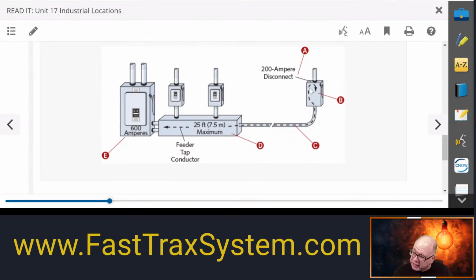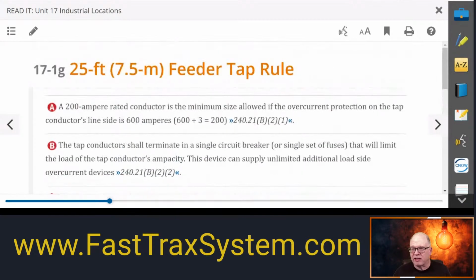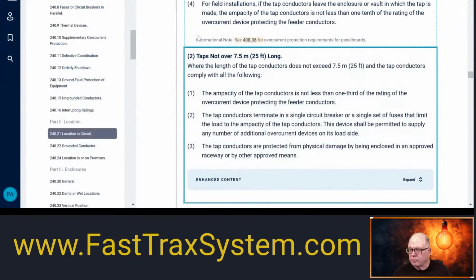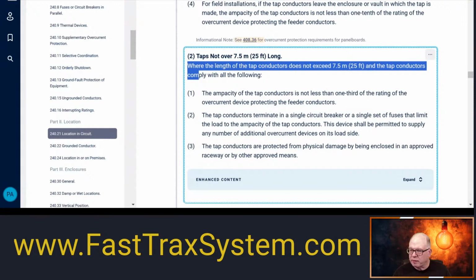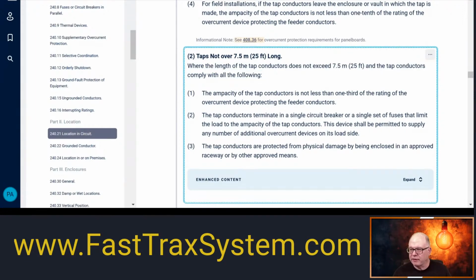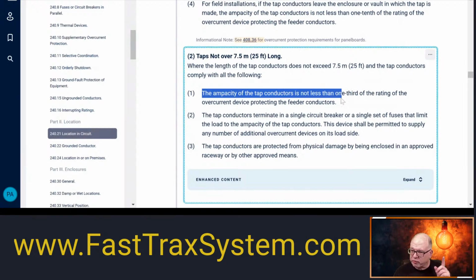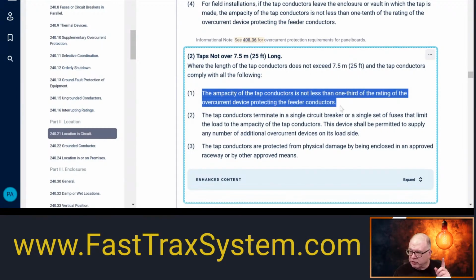All right, so right here, 200 amps. But let's see what the code says about that, because what do we say in our program? Anytime you see these chevrons, we want to make sure that we go look it up in the code. So let's look at the rules. Where the length of the tap conductor does not exceed 25 feet and the tap conductors comply with all of the following. First one we just saw. So this 25 foot of conductor that's tapped onto a feeder, whether it's at the lugs or onto a conductor, is still a tap. And it says the ampacity of the tap conductor is not less than 1/3 of the rating of the overcurrent device protecting the feeder conductors. Okay, so not less than that.